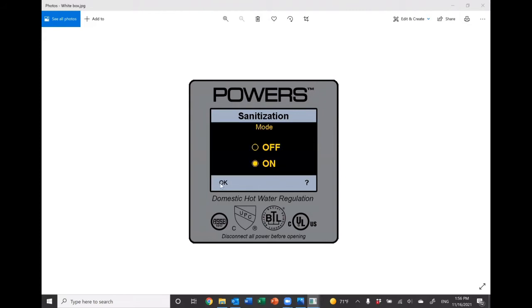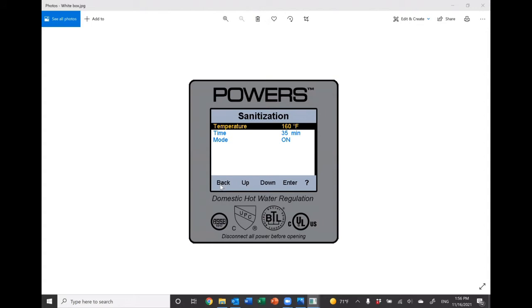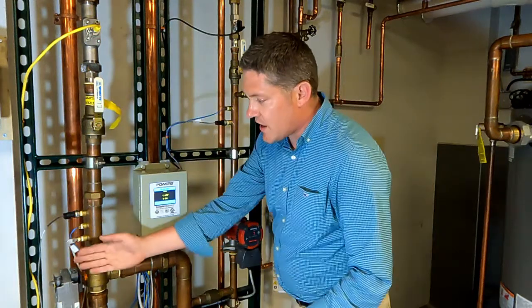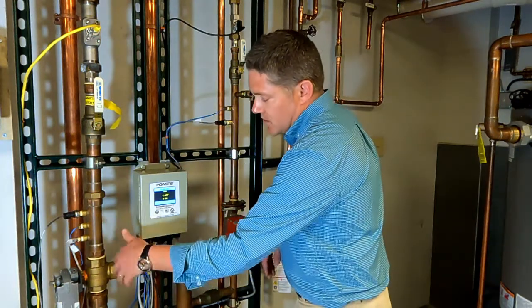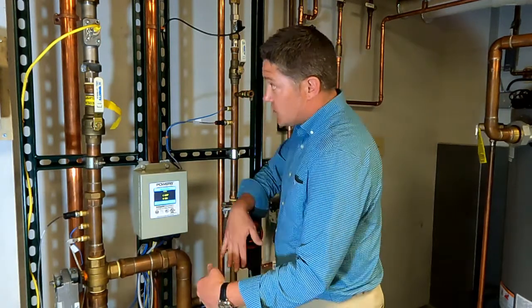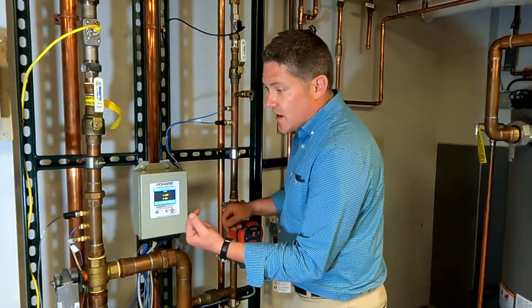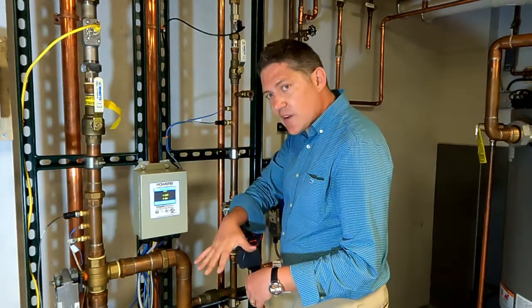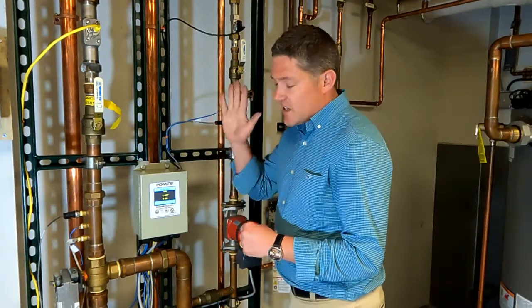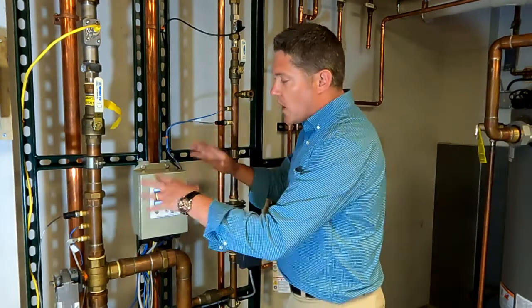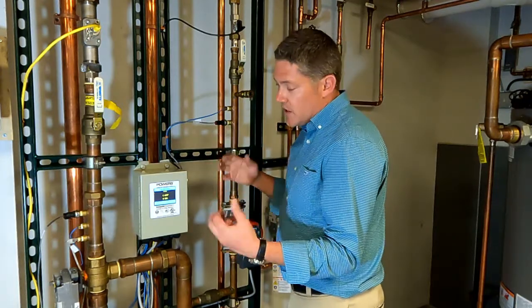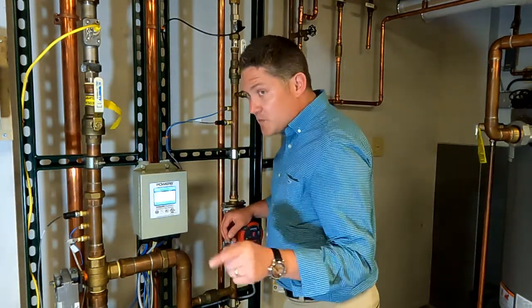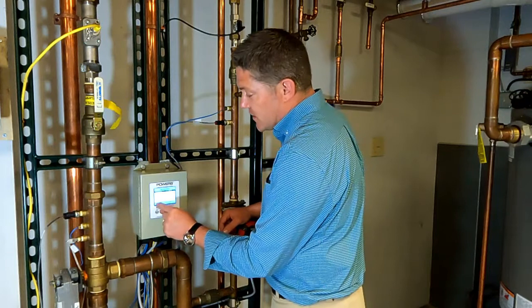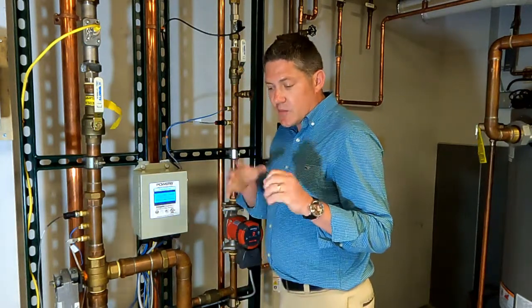Then I go into mode, right, enter, hit on, and then hit OK. And as soon as I hit OK, it's going to start to raise the temperature of the mixed outlet by moving that actuator and that three-port ball valve to raise that temperature up to whatever I set it at. Once it hits that, it'll start a countdown on there. And once it gets down to the end of the 35 minutes, it'll go right back to the parameters of normal operation. That's a much more difficult thing to do on a thermostatic unit.